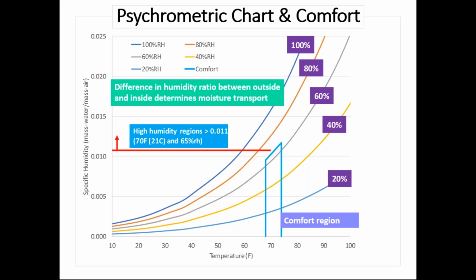The left-hand scale on this, which may be less familiar to you, and the key thing to understand is the left side is telling us how much water per mass of air is contained, essentially the water concentration in air, where the weather person on our TV stations is telling us relative humidity, which may be easier for them to measure and what traditionally they talk about. But when we're talking about moving moisture in and out, this more absolute level, humidity ratio or specific humidity on the left-hand scale, is more useful. Somewhere above about 0.011, which basically means about 1% of the air is water vapor, we start getting to where the evaporative cooling effect on our skin is no longer comforting, and we start feeling less and less comfortable.